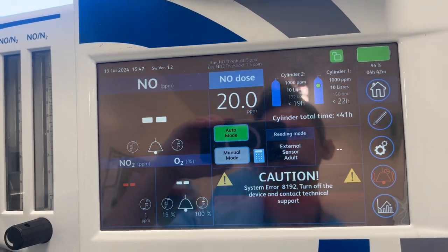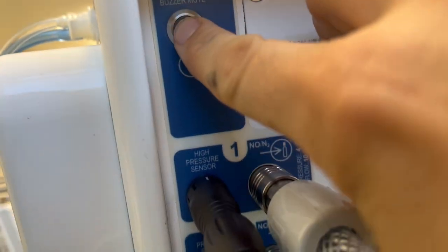The first thing you should do is get rid of the alarm, and you can do this by pressing the alarm reset button at the back of the machine. What this means is that although the nitric is still being delivered at the set level, you now can't see what the sample line is reading, and you can't change the nitric dose that is set.